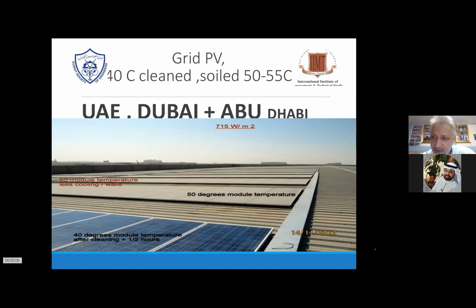Here you can see the soiling effect after haze or sandstorm. And also what's interesting is when you see the parapet walls on the left-hand side, the modules more to the side of the roof have this stuck effect. So they were at 55 degrees, soiled of course, like I said, and the ones nearer to the open space where there's like a self-creating breeze are at 50 degrees. Once they were cleaned up, which you see in the front, they went down to the normal NOCT values. So the best approach, if you see a problematic roof, is of course to check the modules as they are, check the underperformance, clean them, and see first of all if the temperature goes down, second, if the current goes up, and if the output of the system goes up as well.